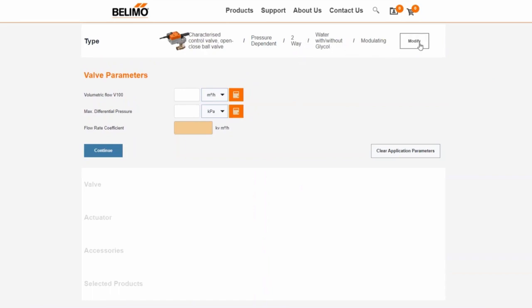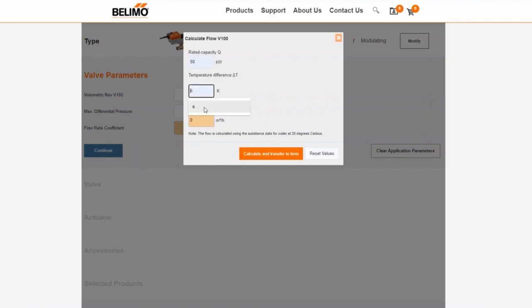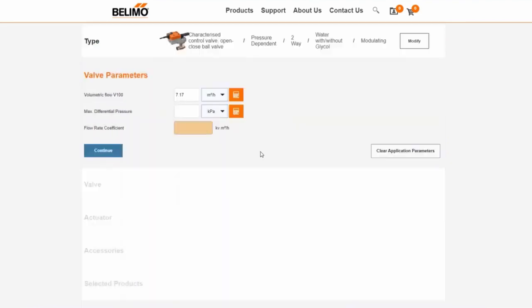Now we come to the flow rate. Here the values are calculated. To do so, click on the calculator symbol. For the nominal power we enter 50 kilowatts and for the differential temperature 6 Kelvin. This calculates the volumetric flow.